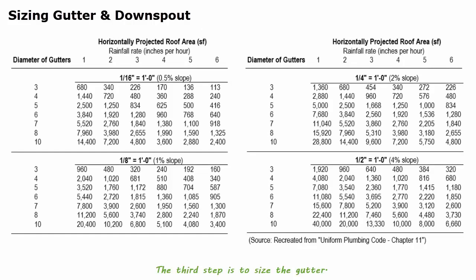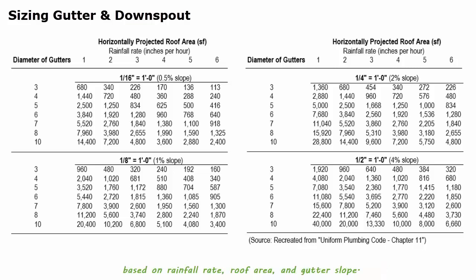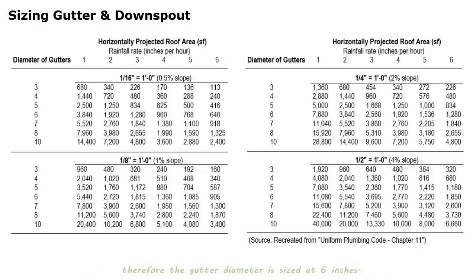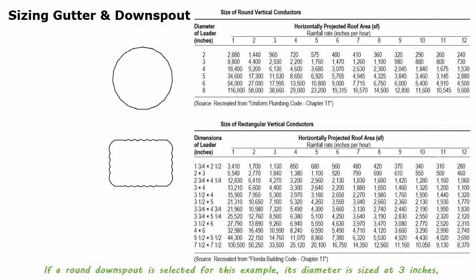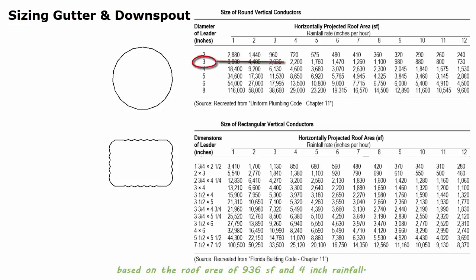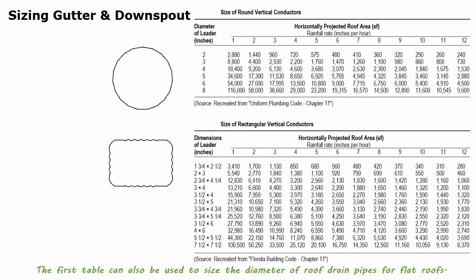The third step is to size the gutter. This table shows gutter sizing data based on rainfall rate, roof area, and gutter slope. With the gutter slope assumed at one-eighth inch per foot, the gutter diameter is sized at six inches. The fourth step is to size the downspout. These two tables show the sizing of downspouts in round and rectangular sections. If a round downspout is selected, its diameter is sized at three inches based on the roof area of 936 square feet and four-inch rainfall. The first table can also be used to size the diameter of roof drains for flat roofs.